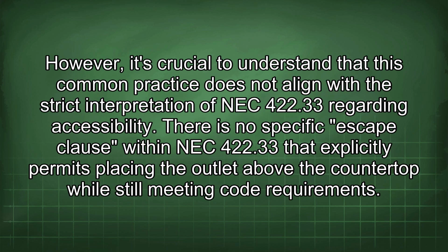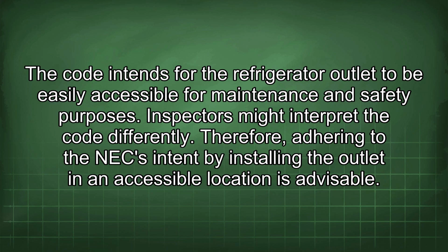However, it's crucial to understand that this common practice does not align with the strict interpretation of NEC 422.33 regarding accessibility. There is no specific escape clause within NEC 422.33 that explicitly permits placing the outlet above the countertop while still meeting code requirements. The code intends for the refrigerator outlet to be easily accessible for maintenance and safety purposes. Inspectors might interpret the code differently. Therefore, adhering to the NEC intent by installing the outlet in an accessible location is advisable.